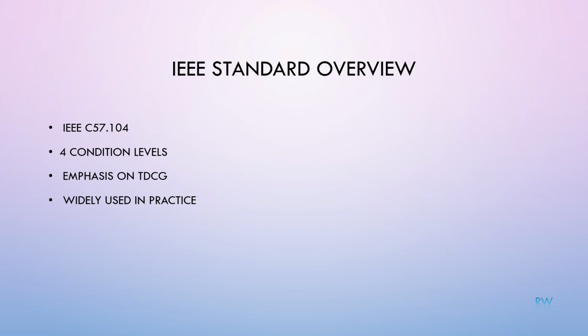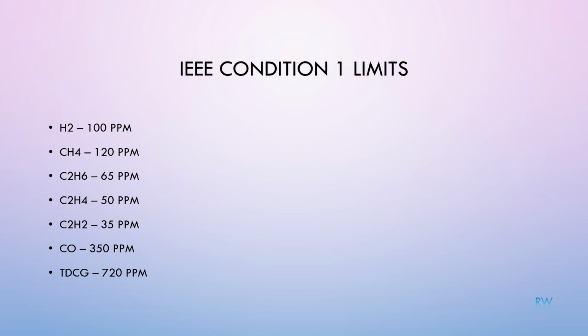IEEE C57.104 classifies transformer condition into four levels based on gas concentration. It emphasizes total dissolved combustible gas, known as TDCG. It provides condition-based guidance for maintenance action. Under IEEE standard, condition 1 represents normal operation. For example, hydrogen up to 100 ppm, methane up to 120 ppm, ethane 65 ppm, ethylene 50 ppm, acetylene 35 ppm, and carbon monoxide 350 ppm. TDCG up to 720 ppm is considered normal.